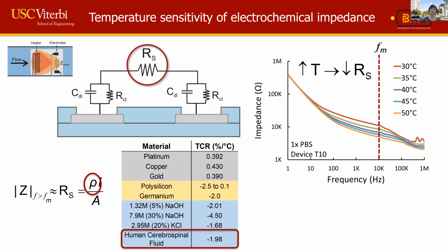The approach we take here is to use the cerebrospinal fluid as part of the sensing circuitry. We have electrodes that are exposed to the fluid, and in this system a double layer forms. This is the equivalent Randles circuit that describes what's going on at the electrolyte interface. What we do is heat the fluid up, and the heat is carried by the flow towards a pair of open sensing electrodes. If we look at these sensing electrodes at high enough frequency, we essentially bypass the double layer capacitance, and so effectively we're looking at just changes in the solution resistance.